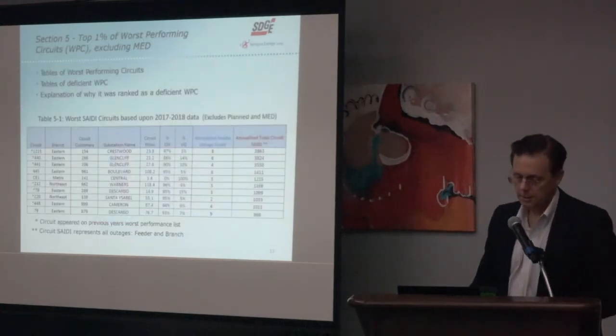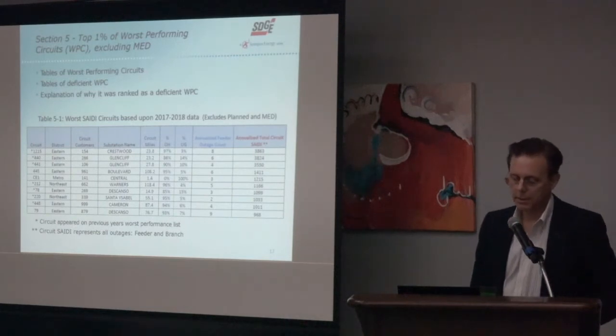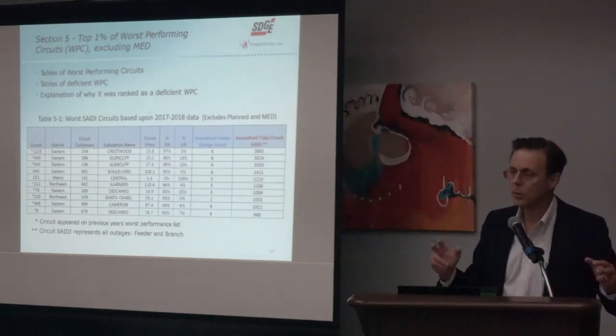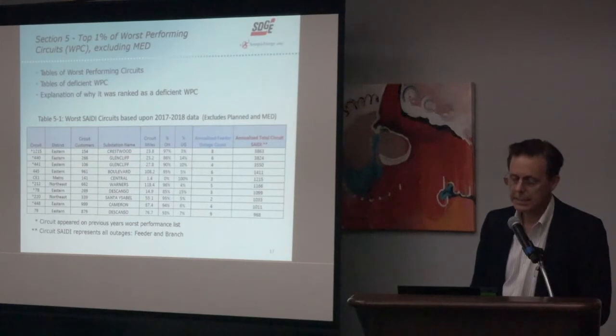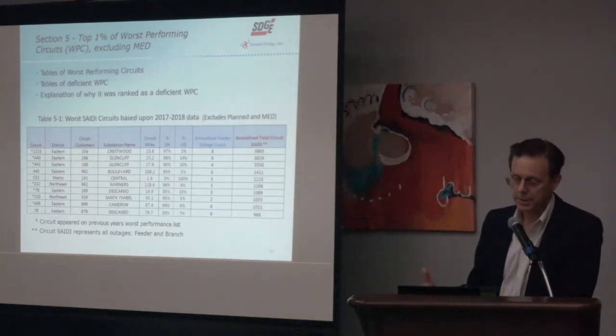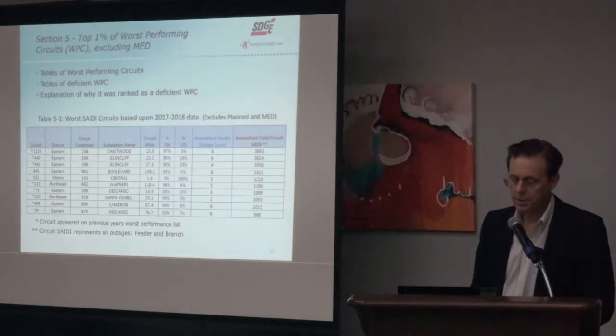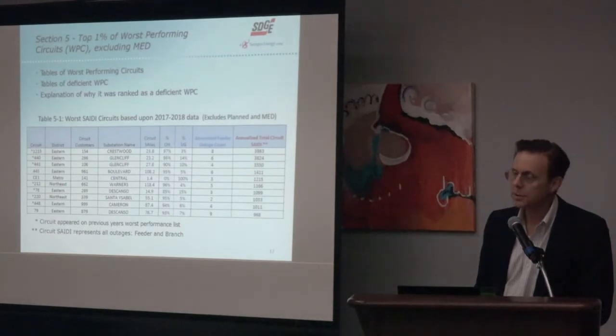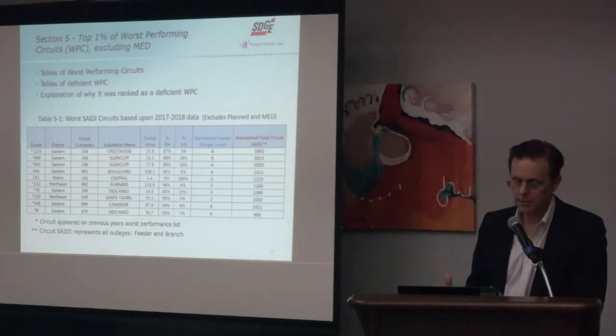One other thing we tend to look at is which circuits are getting hit with the most frequent outages. We call those the worst performing circuits, or WPC. In this chart, excluding the major event days, you see a lot of circuits represented from the eastern and northeast districts. There's only one circuit outside that group, from the metro region - one of the downtown circuits called CE1, which has become troublesome because a lot of the equipment is reaching the end of its service life.